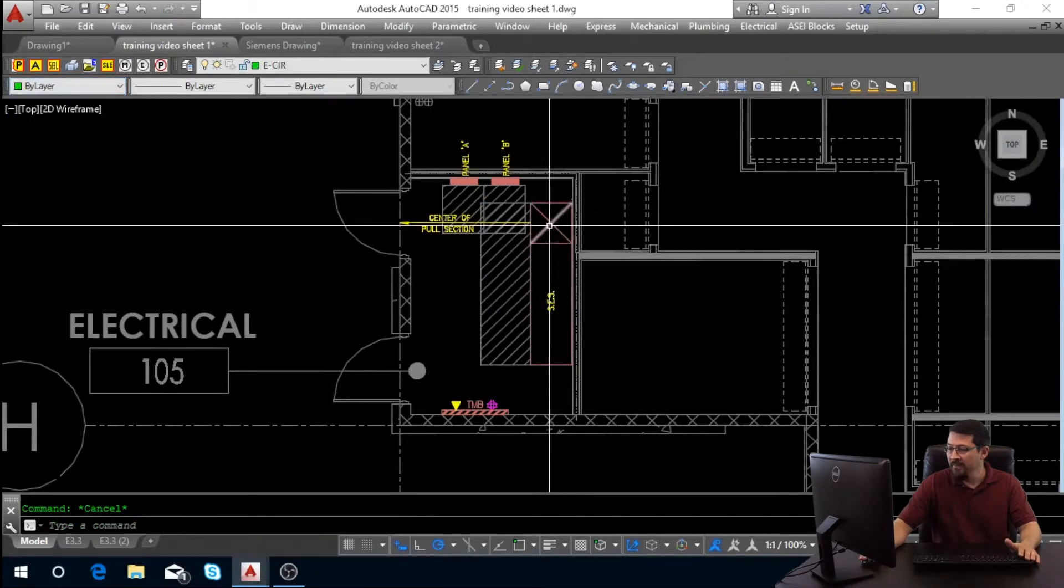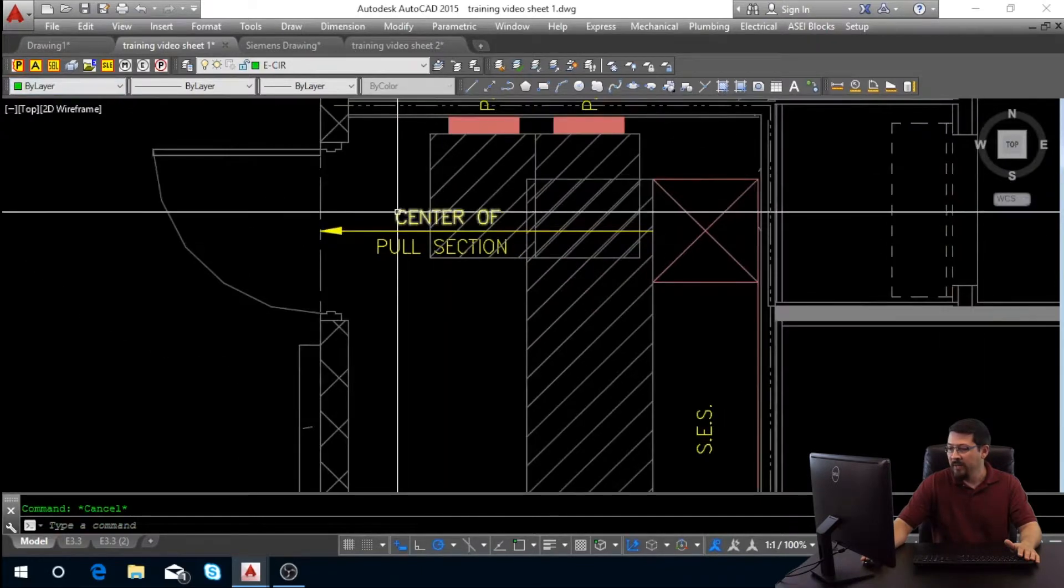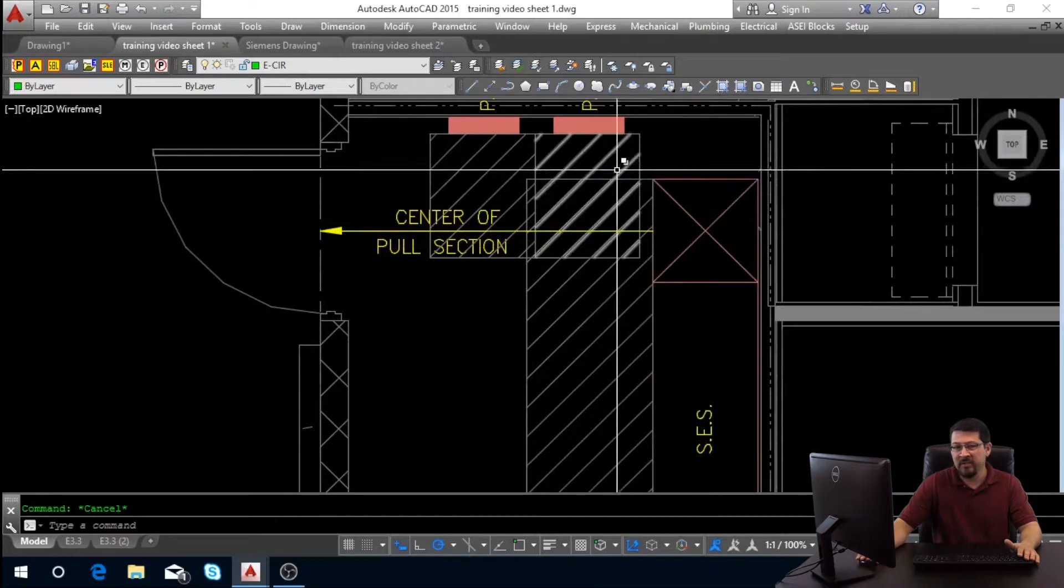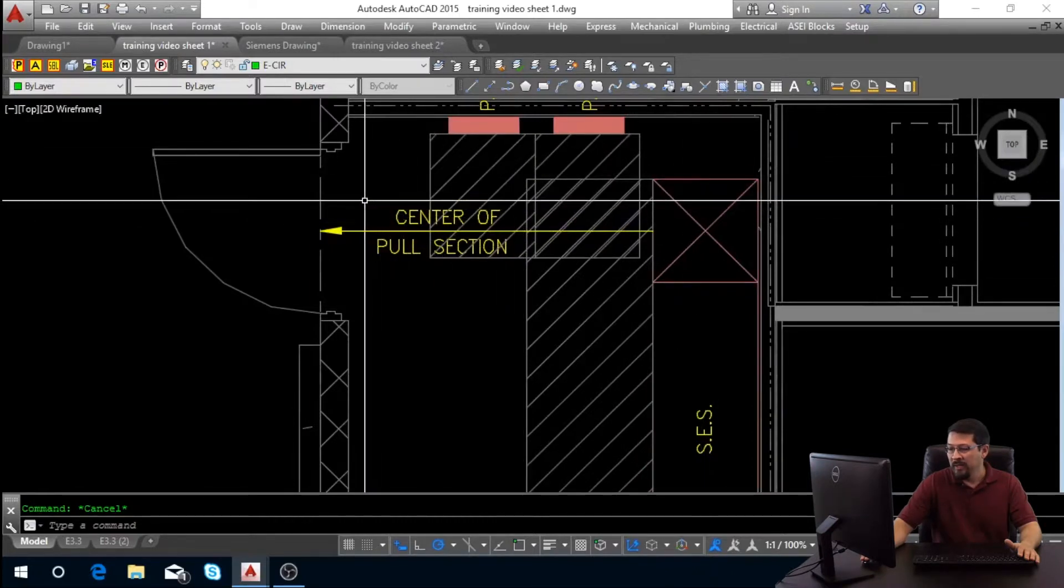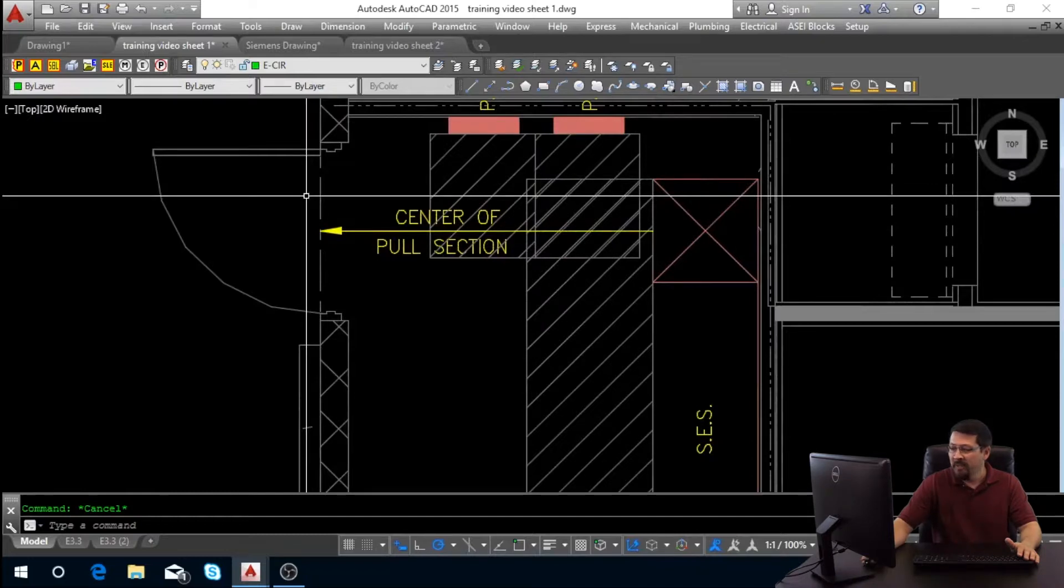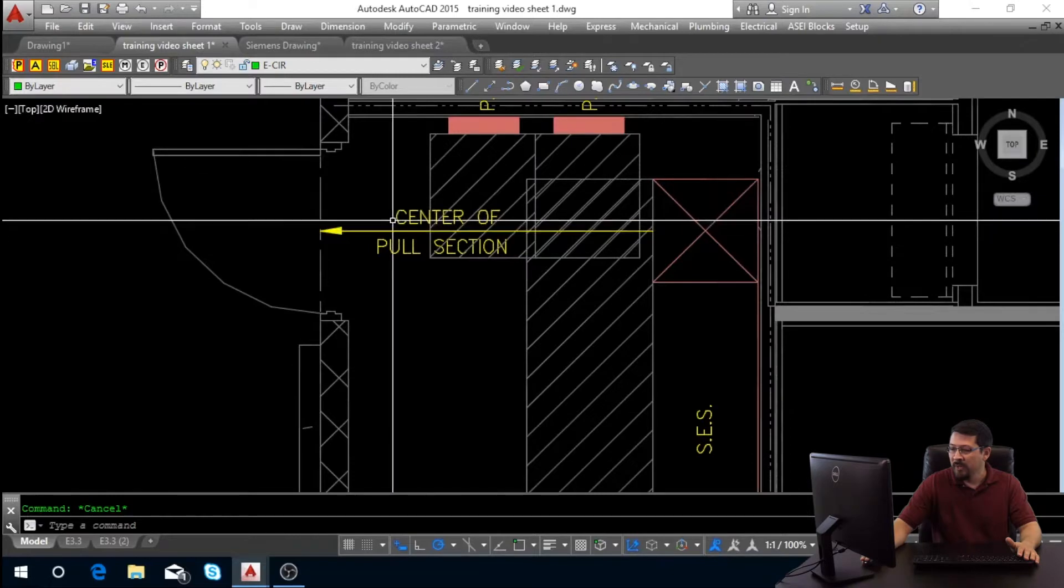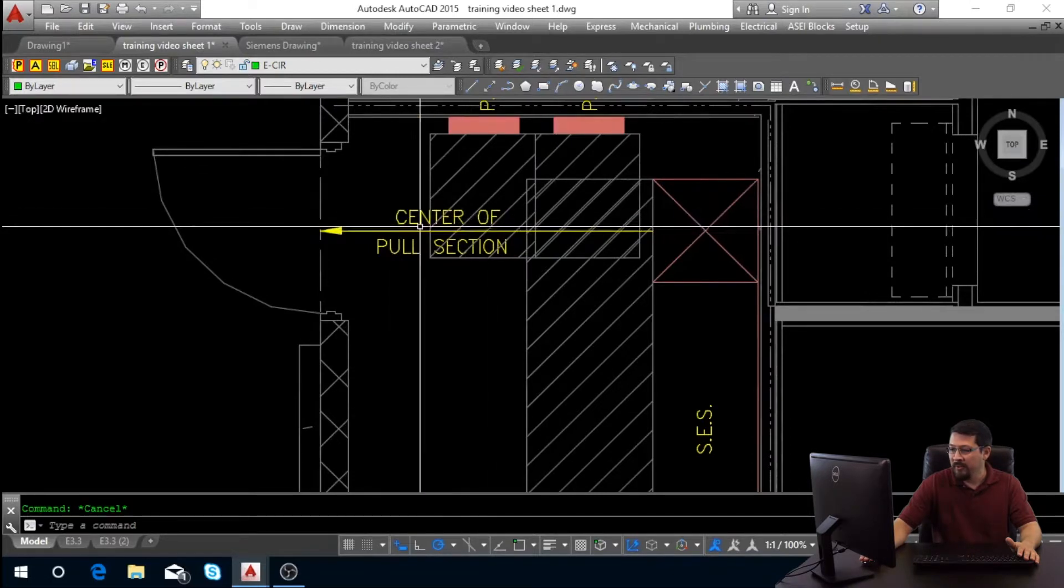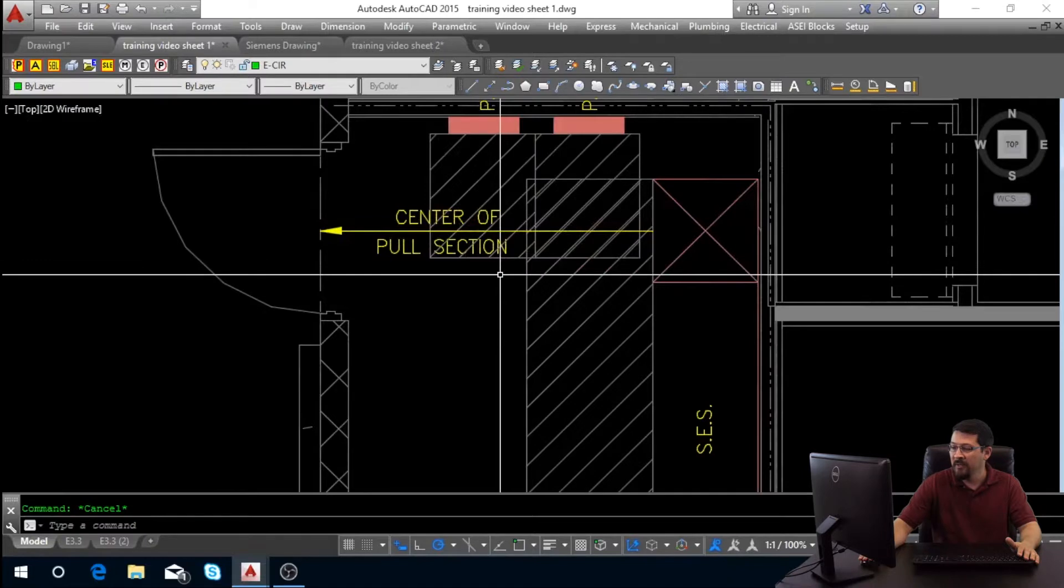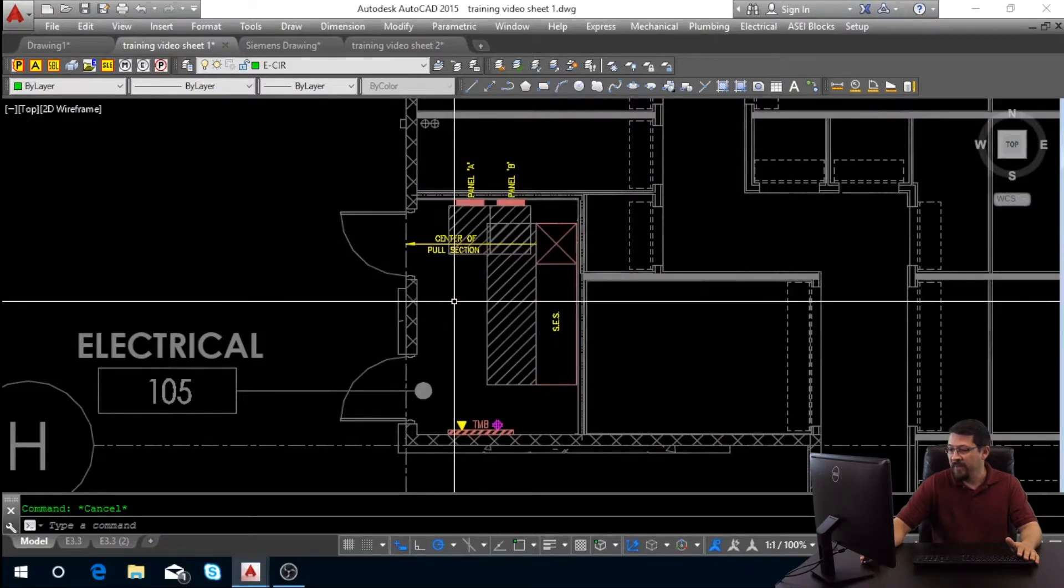Once you have that drawn in, what we want to do is make sure that this pull section is centered in the door. This is a SRP requirement that we've adopted as a company. This just helps them be able to back their truck up and pull the wire for the service entrance from the transformer. So we want to clearly mark that with an arrow center of pull section, just how I have shown here. And that's it for your SES.